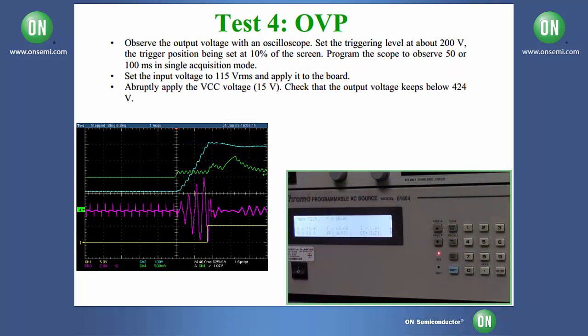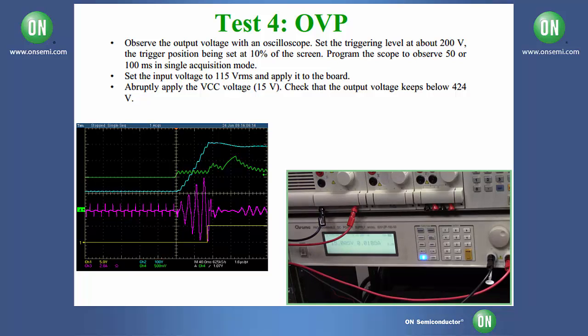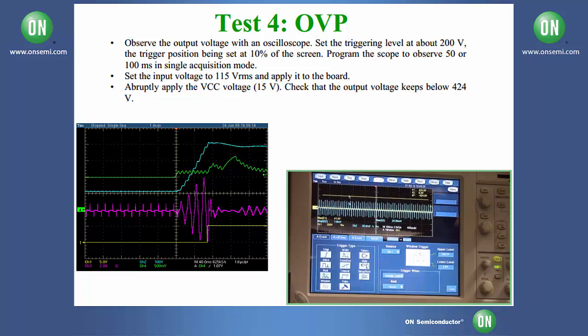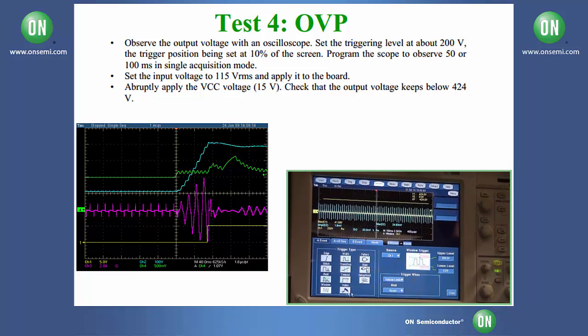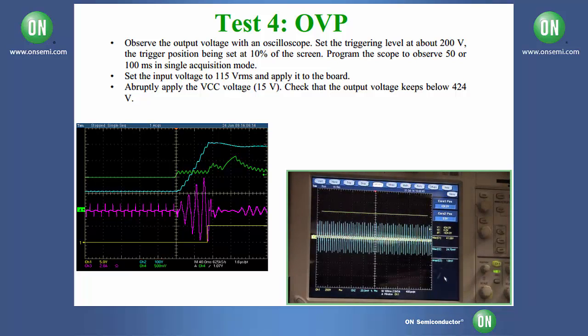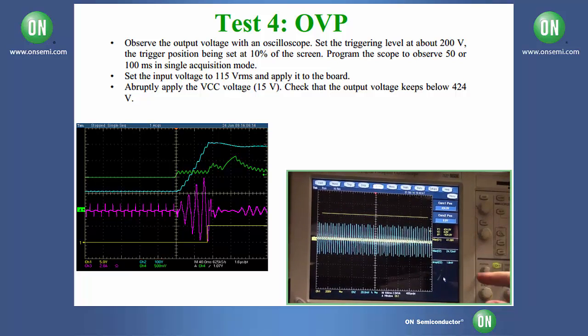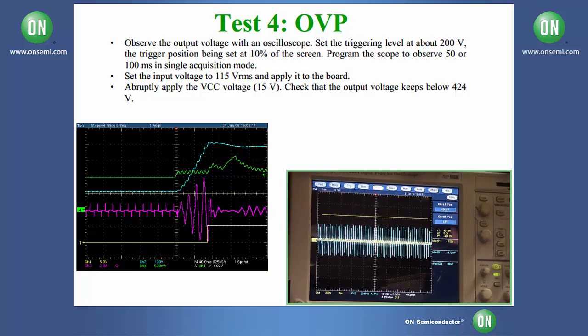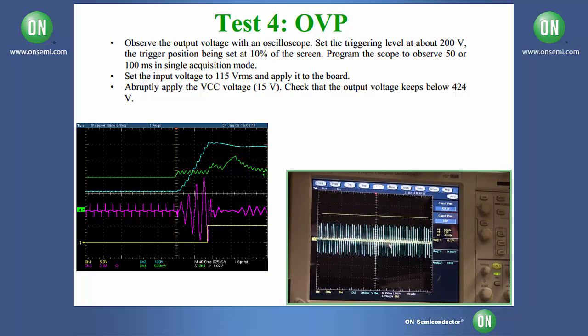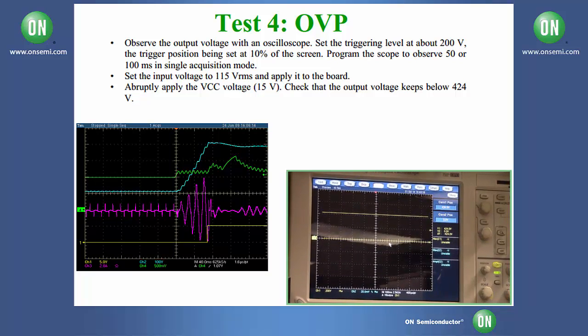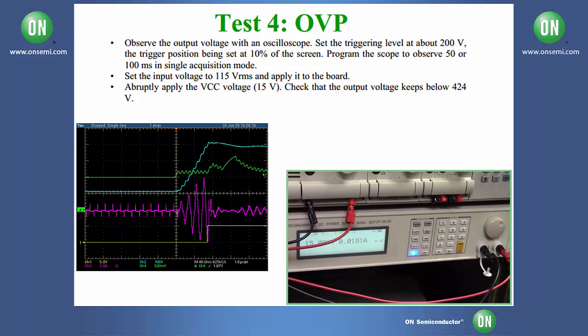And for test 4, first we're going to set our AC source back to 115 volts AC. And next we're going to go ahead and turn off our VCC bias voltage. Now we're going to set the trigger on our oscilloscope to window mode, and the trigger will occur outside the limits of 200 volts. And we're also going to make sure to compress the scale so that we can see quite a bit of our waveform on our oscilloscope. And now we're going to place it into single acquisition mode. And now we'll turn our VCC bias voltage back on.